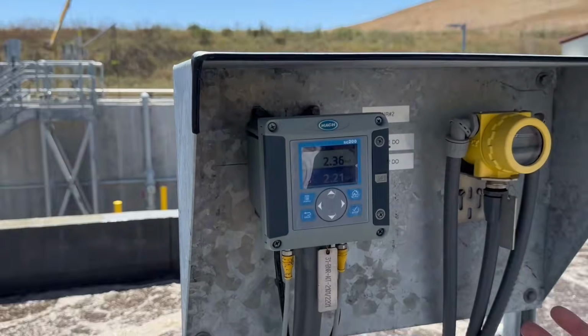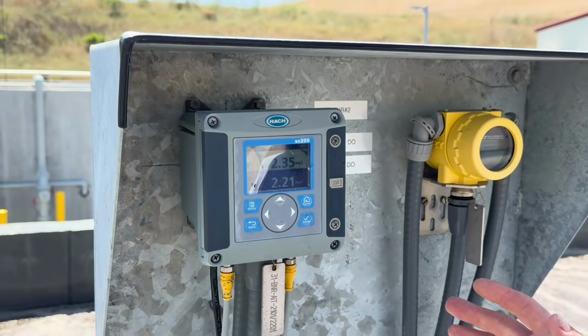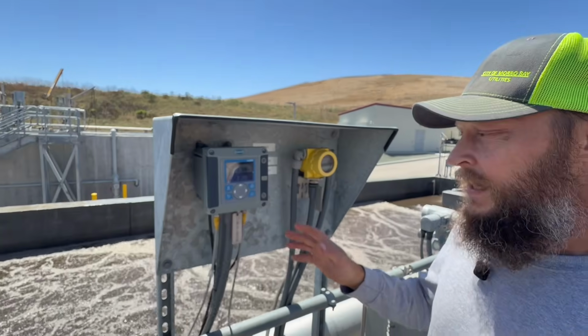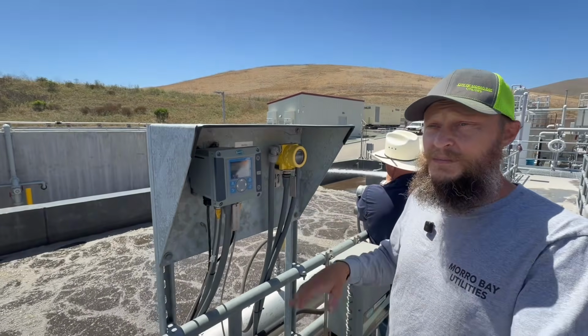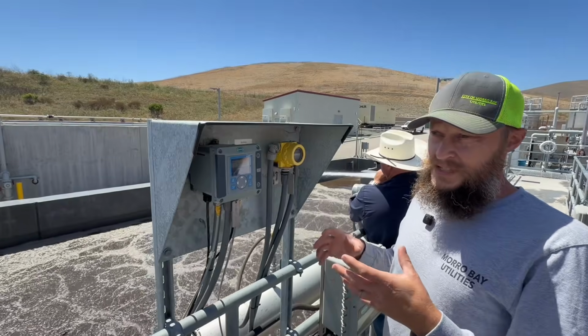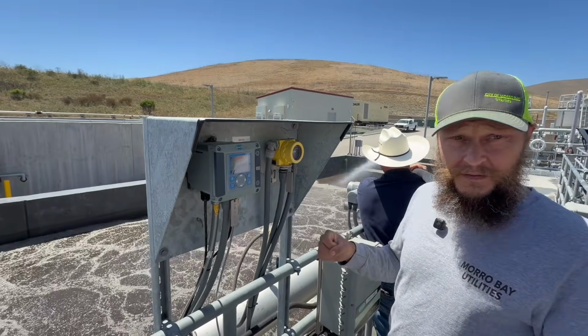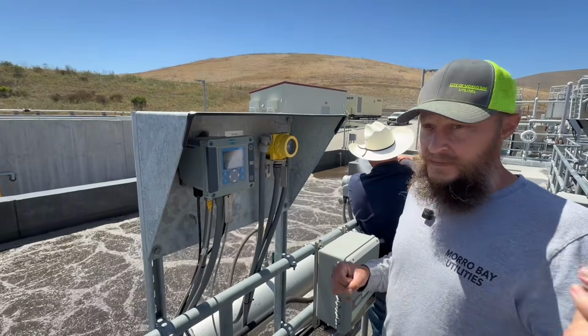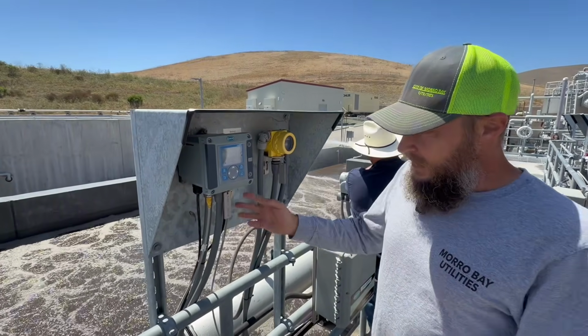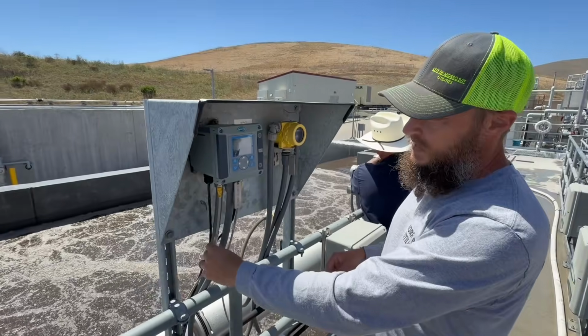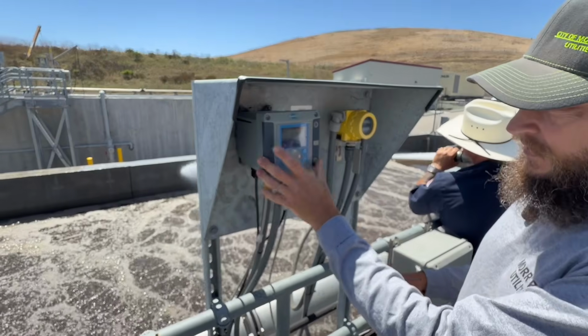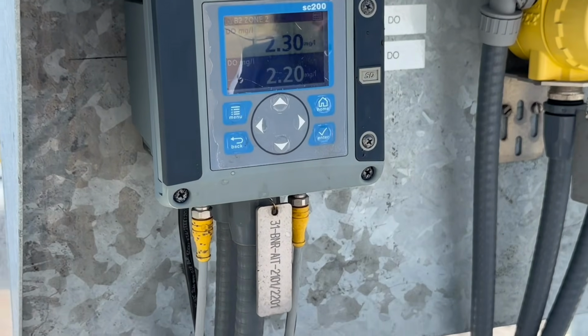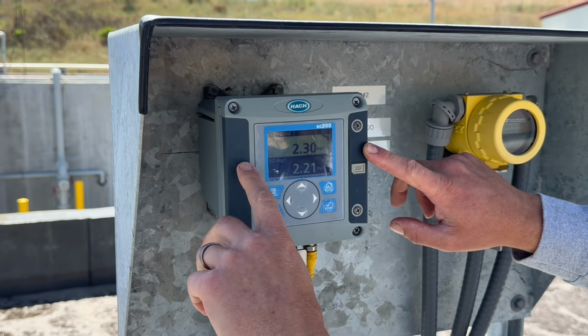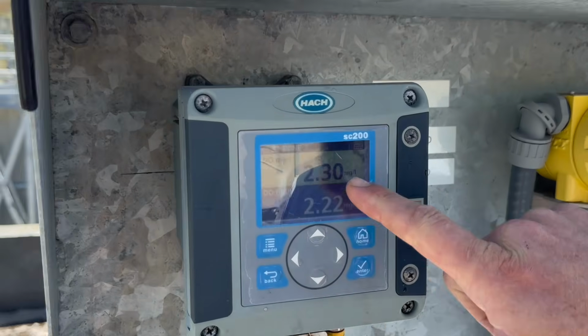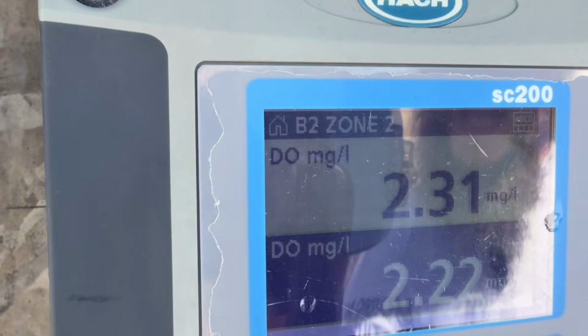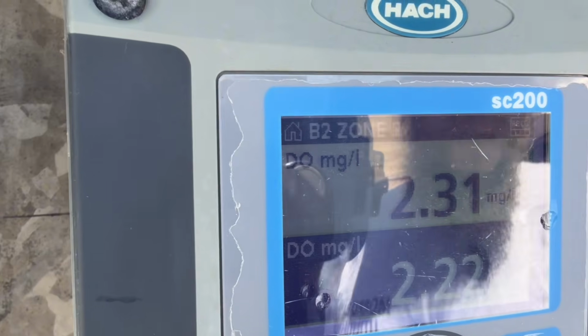This is a Hach DO probe. So what I'm looking at right now is what we refer to as the transmitter. The transmitter is not the sensor itself. It's actually what's transmitting the signal from the sensor. Some sensors have integrated transmission, so it just comes right off the transducer and then connects to the PLC. But here, in most Hach setups, the sensor comes into the transmitter and then out, and that goes back to our SCADA system. So if you remember, we were looking at Basin 2, Zone 2, so we can see that on the transmitter, and we're reading 2.31 milligrams per liter.